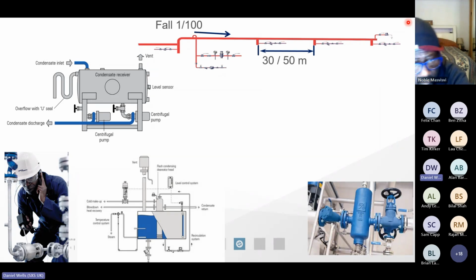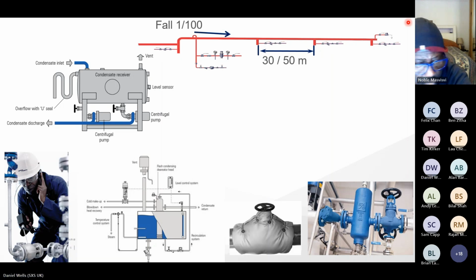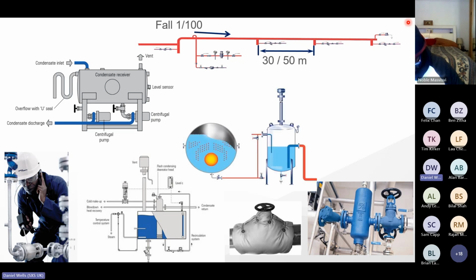Simple things like separators. Separators dry the steam. The drier the steam, the more energy. The more energy in the steam, well, the boiler doesn't have to work as hard. Insulation, reduce that heat loss. 30, 40 years ago, when the steam system was engineered, it likely wouldn't have had insulation because we wouldn't enjoy the payback. But today, we're more educated. We appreciate not only what the payback will be in financial terms, but also the extent to which we can reduce those carbon emissions.